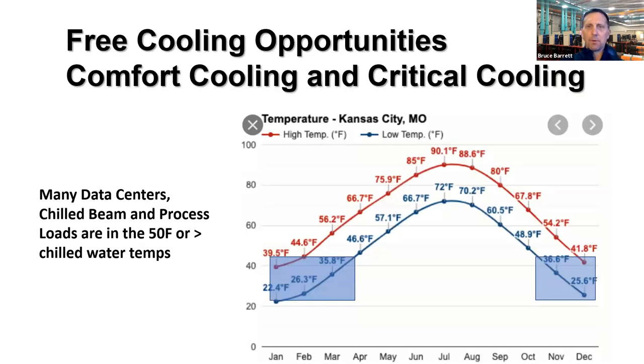So I pulled Kansas City opportunities for free cooling. I just assumed 44, 45 degree leaving chilled water, just to look at the opportunity hours. So I've got those blue transparent boxes at the bottom. January, February, parts of March, parts of November and December. Pretty much all, you know, that's four and a half, five months of opportunity of free cooling at a 44, 45 degree set point. A lot of these data centers don't operate there. They're much higher. So your opportunity hours for free cooling certainly grows. Process coolers or chilled beam. Chilled beam, I've seen temperatures 50, 52 degrees. Again, your opportunity hours continue to grow.